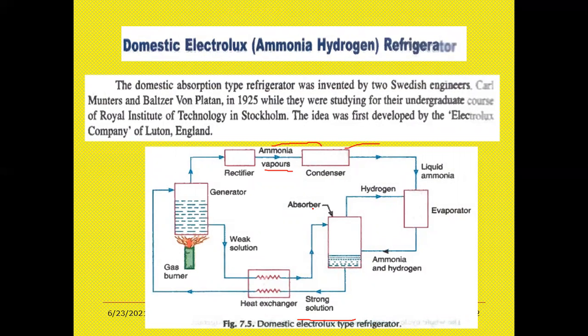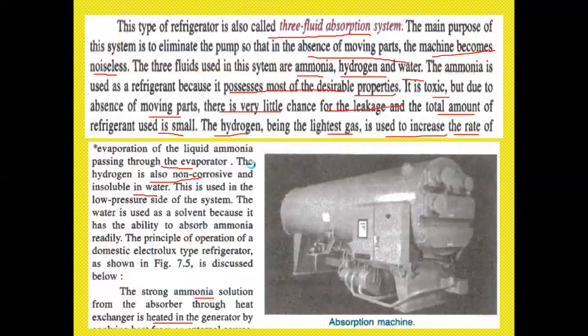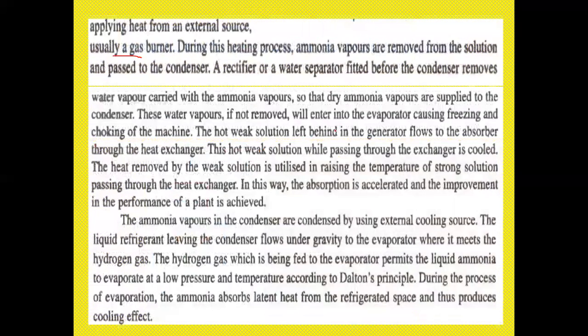Okay, so here if you take the ammonia, from this point, the liquid ammonia is going into this heat exchanger and going into the gas burner. Here it is converted into the vapor form, so it is passing into the condenser through the rectifier. That is this point what they have written. So during the heating process, the ammonia vapors are removed from the solution and passing to the condenser.